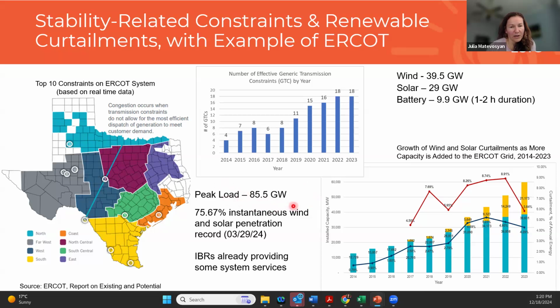Instantaneous wind and solar penetration that they have achieved so far is 75%. If you remember the first slide that I was showing, we are at this stage where you need some additional measures on the grid to maintain this high share of grid-following inverter-based resources. Inverter-based resources already have some stringent requirements applied to them: ride-through requirements, primary frequency support requirements, voltage support requirements. They're still all grid following, so there are no grid forming requirements yet, though ERCOT is working on it. And still with that, there need to be some additional measures to maintain stability.